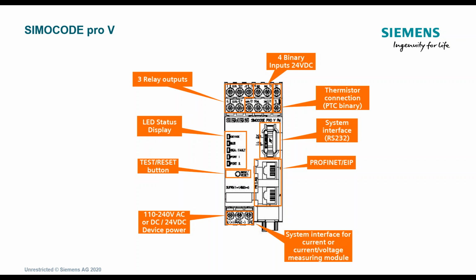And then here's the communication interface. This interface is where we take a ribbon cable from here and then go to the expansion modules for analog, digital, or temperature or earth fault. And then on the Profinet/Ethernet IP version, it has 2-port switches so you can daisy chain or do star topology or token ring. We can do all types of different communication topologies with that. Then we have a system interface underneath where you plug in the CT or PT-CT combination that you need. And then the SIMOCODE has 2 flavors, 110 to 240 volt AC or 24 volts DC for excitation of the unit itself.